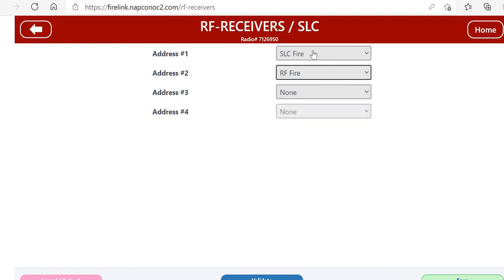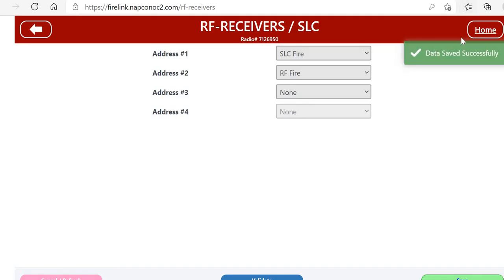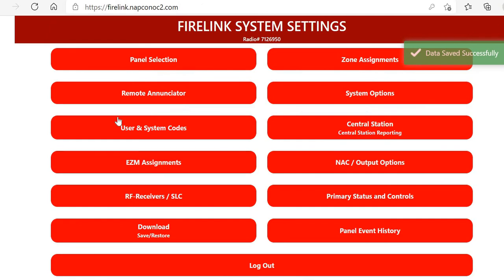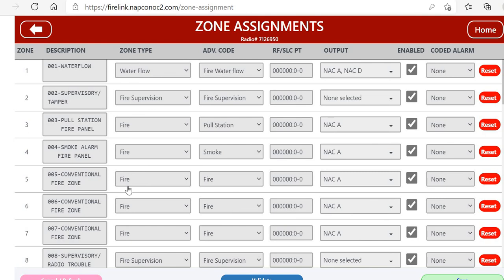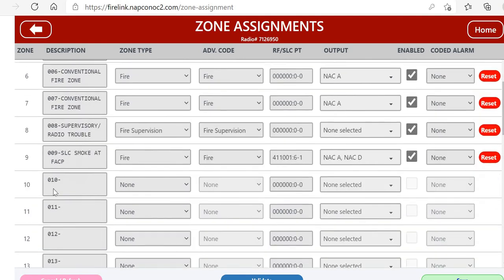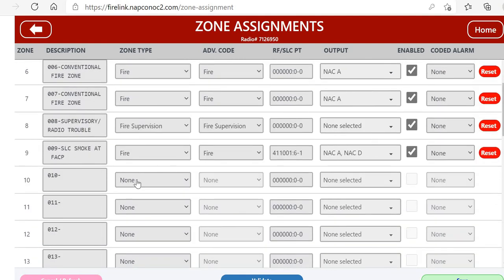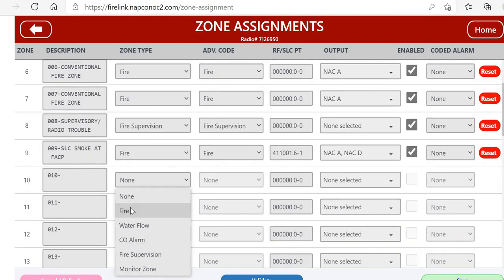We already have SLC Fire, so we're going to make address two our RF Fire. Now remember, these need to be in order, so if you didn't have SLC and you were just doing wireless, that would be on address one.